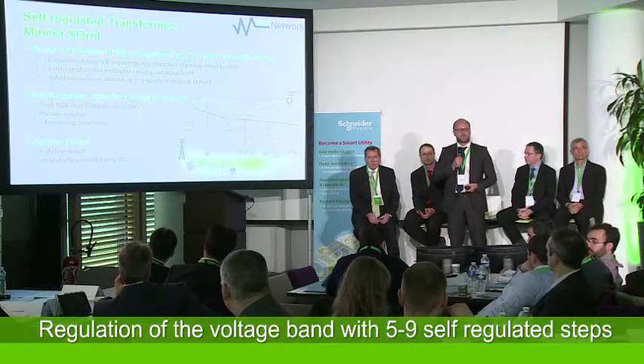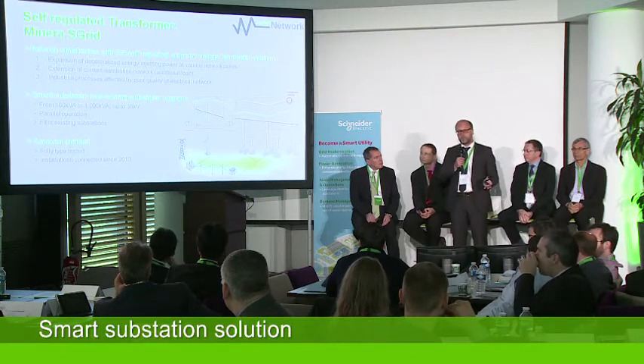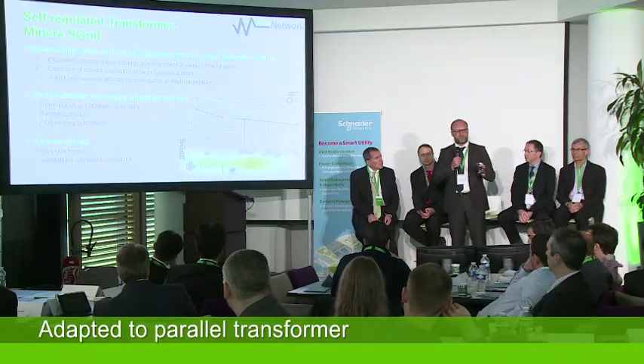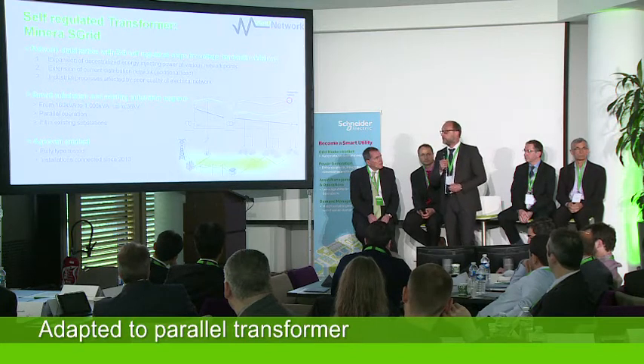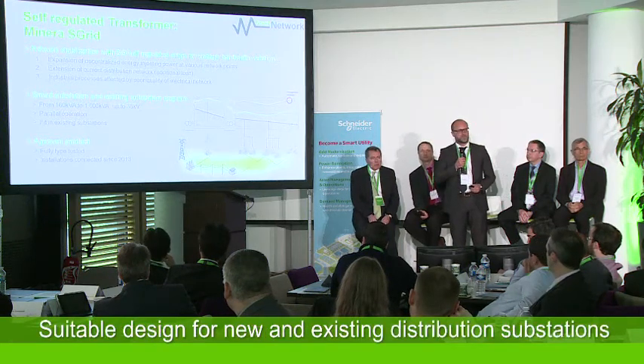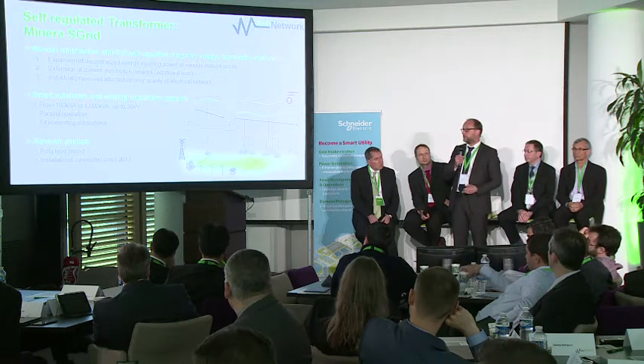This solution can be used for smart substations including all communication, but also to upgrade existing substations. We have solutions going up to 1,000 kVA — 1 MVA — and up to 36 kV, covering the complete voltage levels. For requirements in Europe, particularly Germany, Switzerland, and Austria, where parallel transformer operation is common, we support that as well. These transformers are not much bigger than standard ones, so they can fit into existing substations.